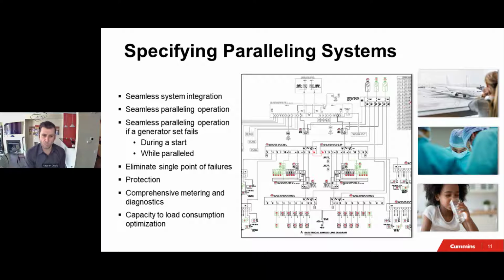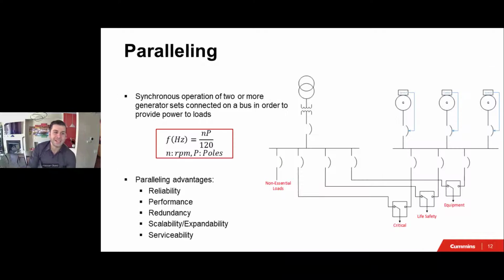And we want to have some kind of capacity to load consumption optimization to reduce the wear and tear on a generator set and also reduce fuel consumption. So those are the high level items that we want to think about when we're specifying this paralleling system. So now that's out of the way, let's start diving into the details. We're going to start with paralleling.